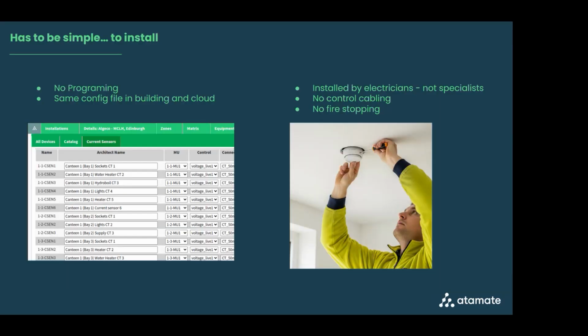Not only does it have to be holistic, joining up all this information, the next thing is it has to be simple. Ideally you don't want any bespoke programming, and ideally you want the same config file used in the building as used in the cloud. If you don't do that, you're in a world of pain, saying I'm in room 27 and I want to read temperature sensor number 46 and compare that to room 32, and it gets quite messy and complicated. So really, all the data needs to be properly labeled and easy to manage coming out of the building.